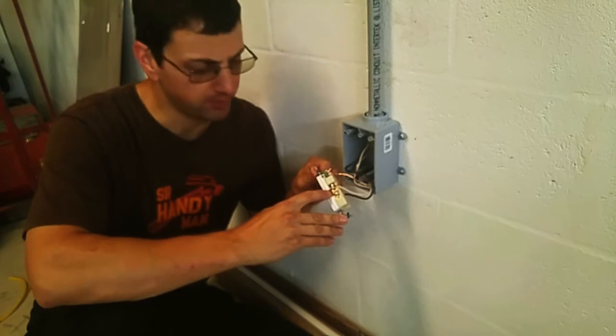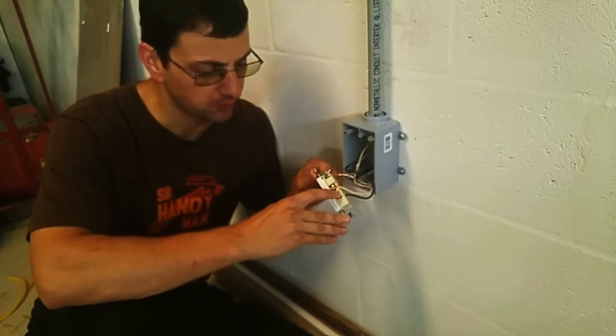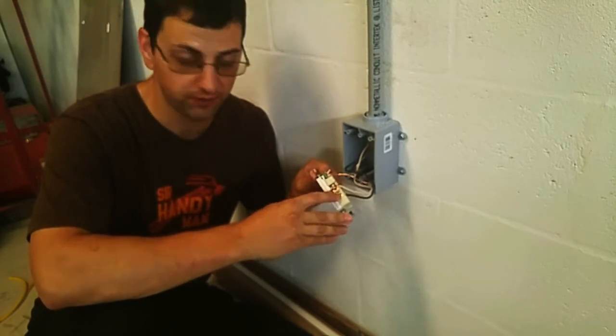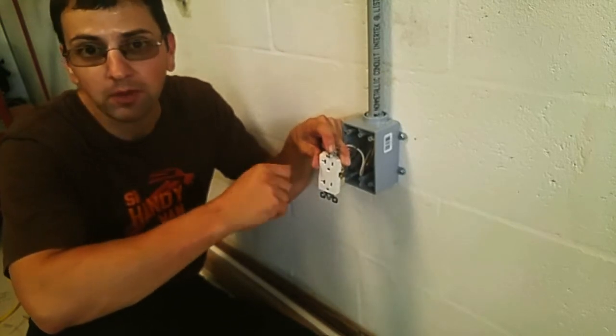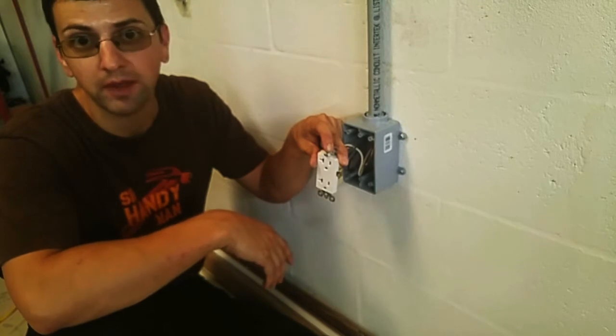There's a little metallic tab here between the bottom screw and the top screw. That tab connects the two together. It's also what connects the bottom outlet to the top outlet. Snapping off that tab will let you control the outlets independently.